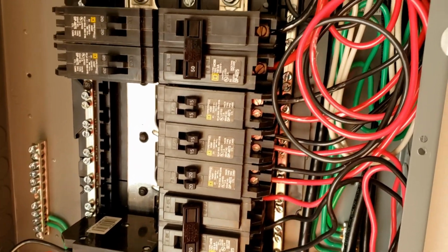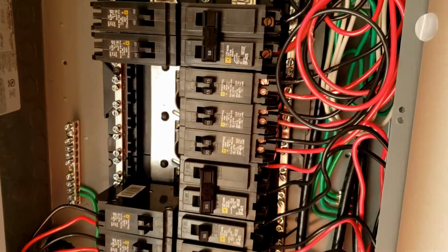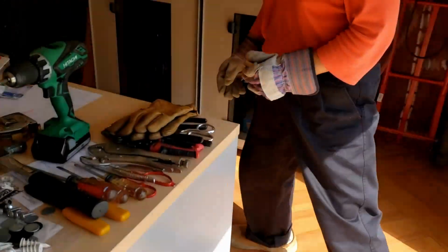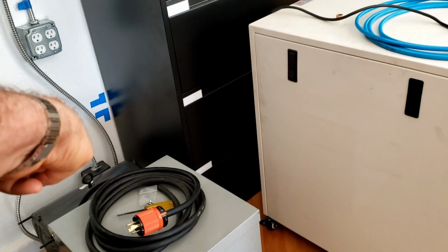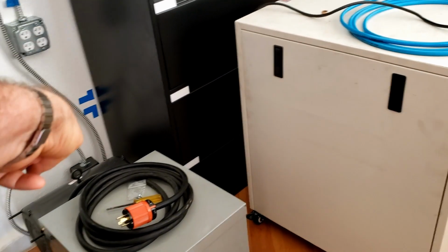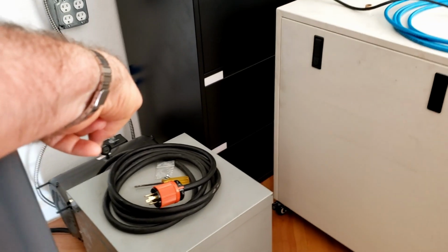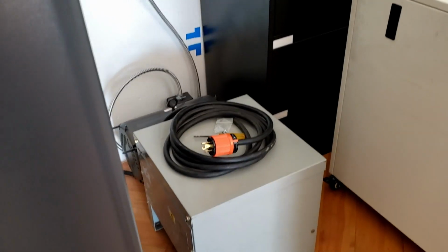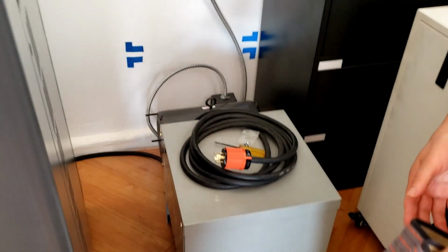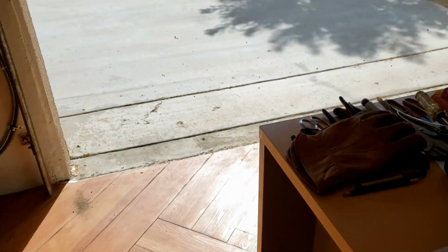Okay, now if we turn on the 50 amp breaker, come over here and stand by the motor. Just listen - that motor should not turn on. If it turns on, tell me it's on and I'll quickly turn the power off. It should not turn on until I turn on the panel up there, so we just want to make sure all the wiring is correct.